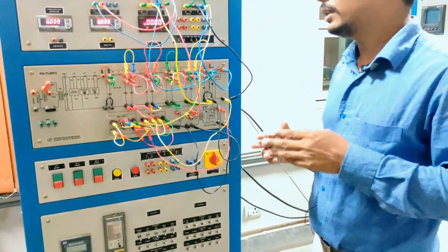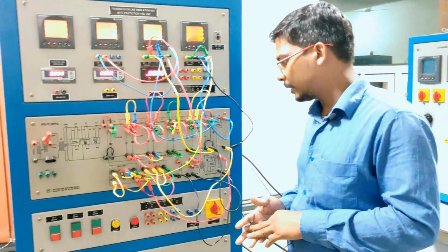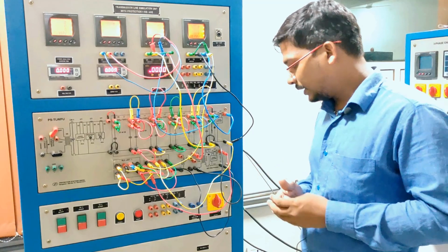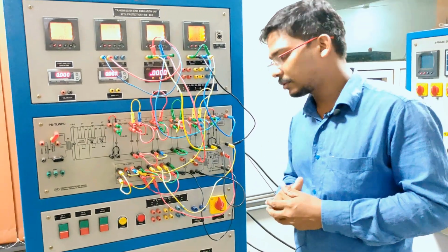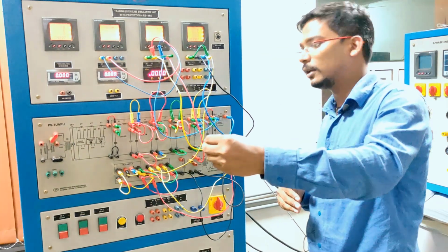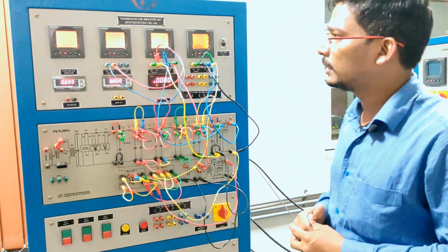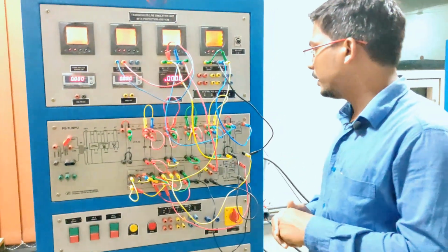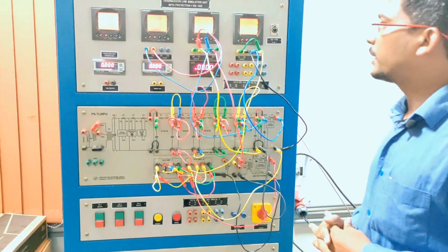Let's say the RLC unit is taking the power of 100 var. Now to increase the power from 100 var to more, we have to increase the tap changing. So we are increasing the voltage across the compensator, and that indirectly increases the power which will be taken from the transmission line, that is the reactive power.